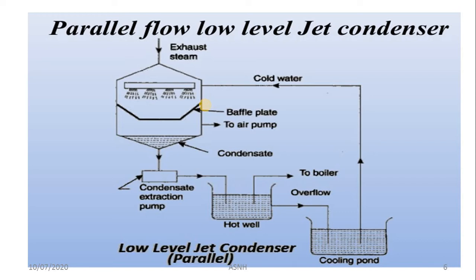Now we will discuss the working. The name itself indicates parallel, which means the direction of the steam entering and the direction of the cooling water entering is the same. The steam and cooling water enter in the same direction and mixing takes place. So the name is given parallel flow jet condenser. Why is it called parallel flow? Because the direction of the steam entering and the direction of the cooling water entering is the same. So here the steam goes from the boiler to the turbine, and from the turbine the steam enters the condenser shell, while simultaneously cooling water comes from the cooling tower or from the cooling water tank.